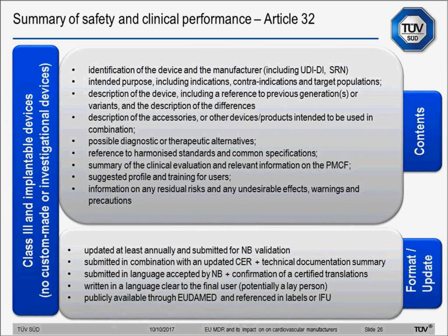So the summary of safety and clinical performance should include a detailed description of the device, its intended use, possible alternatives for the treatment of the same condition, and it should provide reference to the standard and the common specification to which the manufacturer claims compliance, and suggestions regarding the required training and the profile of the user. A key part of the document is a summary of the clinical evaluation, including relevant information from the post-market clinical follow-up. The summary of safety and clinical performance is not a static document. It should be prepared the first time for the approval of the product and then should be updated at least annually. The document will have to be validated by a notified body and should be referenced in the instructions for use, and it should be a public document made publicly available through the EUDAMED database.